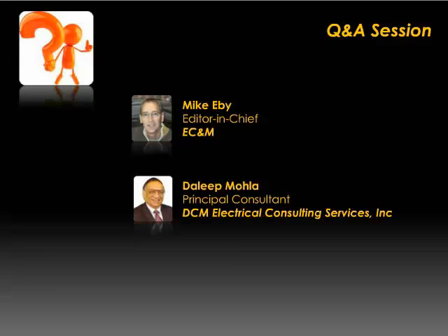Okay, can the system and equipment BIL be exceeded when applying HRG? Absolutely not. Equipment rating and BIL, or basic impulse level, is based on lightning protection. All HRG will do, if you have a phase-to-ground fault, is isolate it. So no, equipment cannot exceed its rating under any circumstances. Okay, great point.